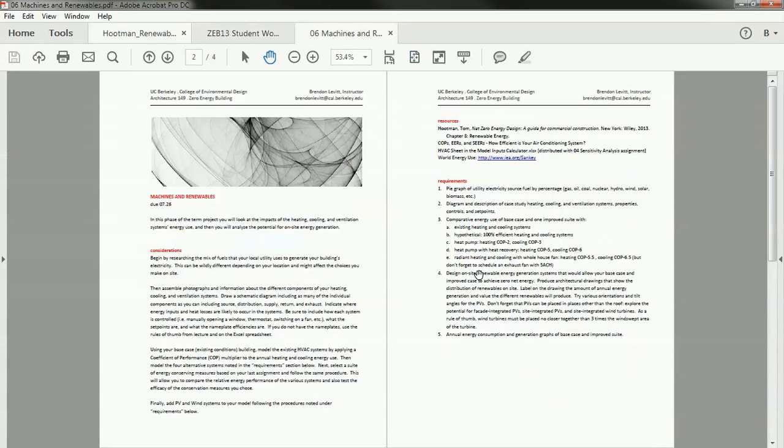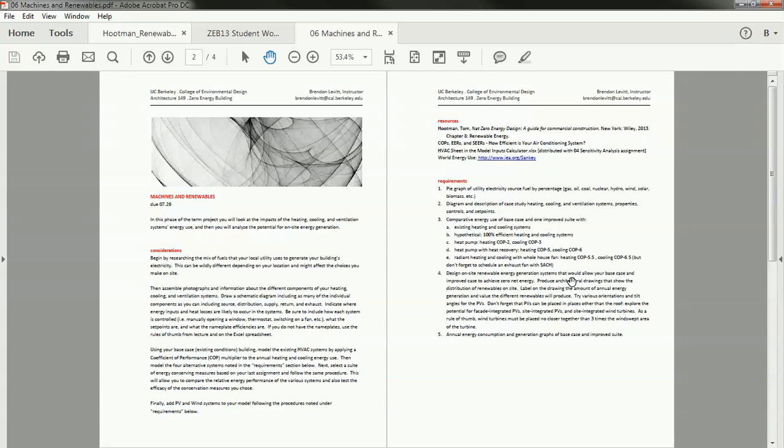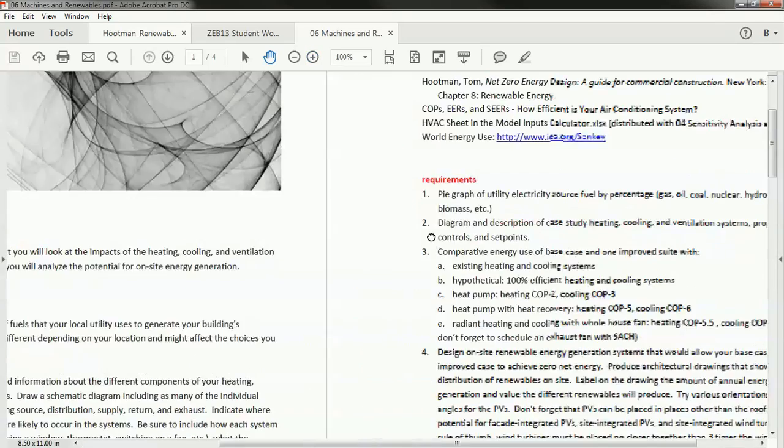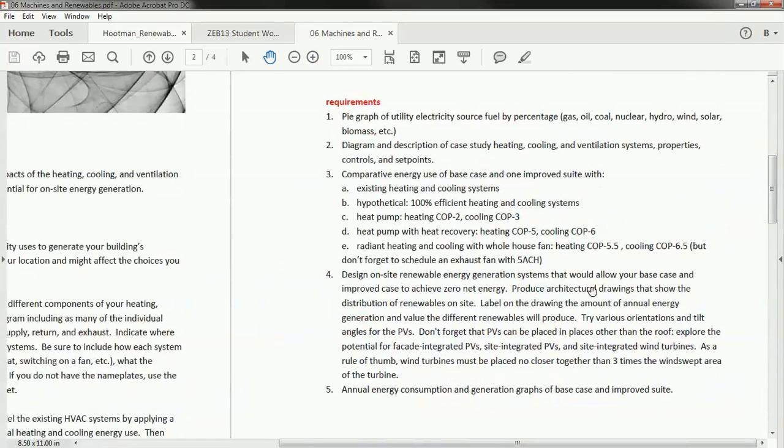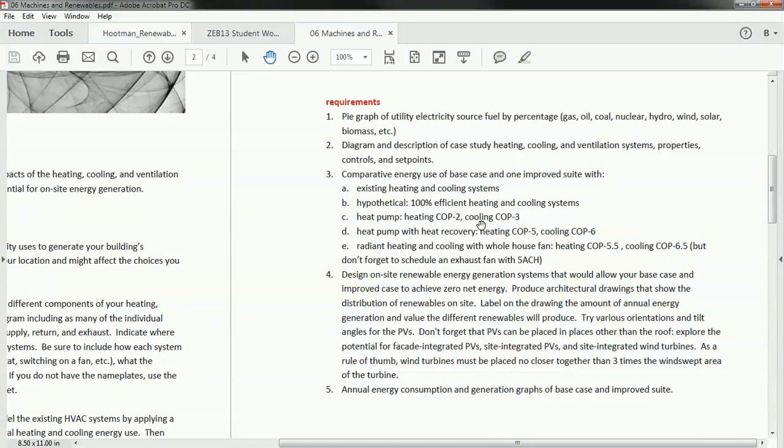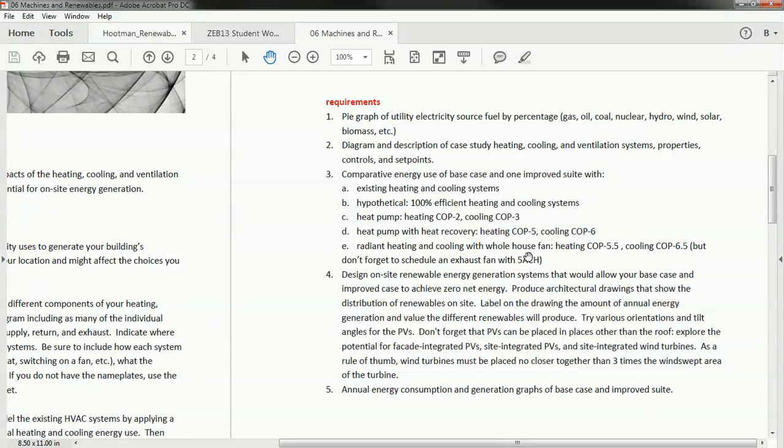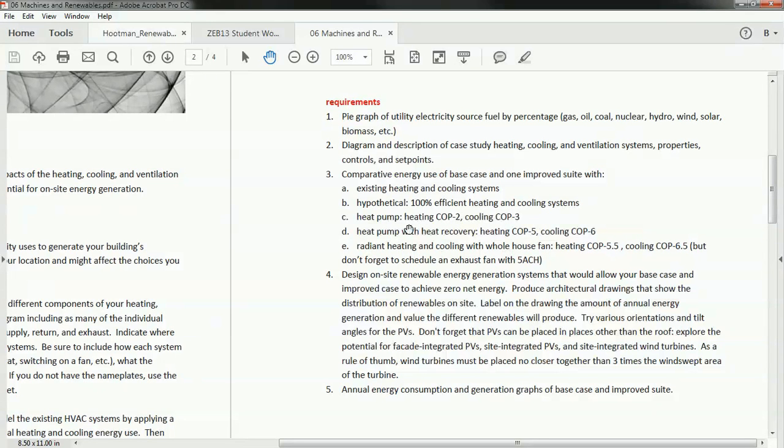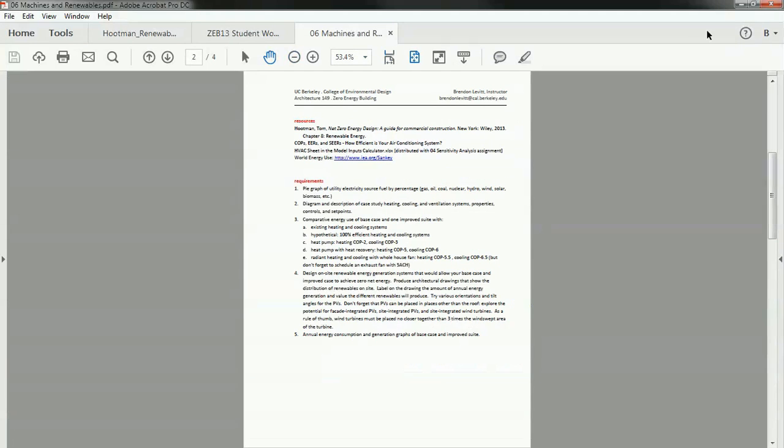Okay, the next part of the assignment is to compare the energy use of the base case, that is how your building is actually designed, to an improved suite with different heating and cooling systems. You can see here I've labeled a bunch of different systems I'd like you to try out. The existing heating and cooling systems, a hypothetical one that's 100% efficient both for heating and cooling, a heat pump that has a COP of 2 for heating and a COP of 3 for cooling, a heat pump with heat recovery that has a COP of 5 and 6, and then radiant heating and cooling with the whole house fan with even higher COP. But you should make sure that you're actually scheduling the exhaust fan and seeing that ventilation energy use. So I'm going to walk you through those. They're quite quick and easy to do.